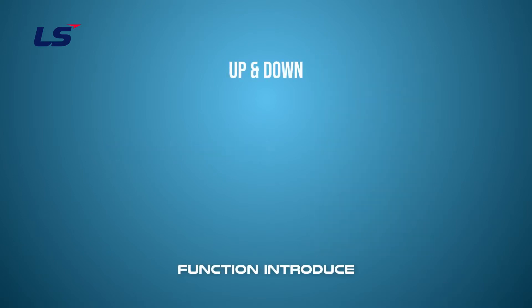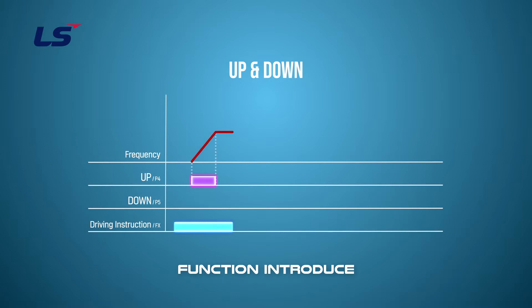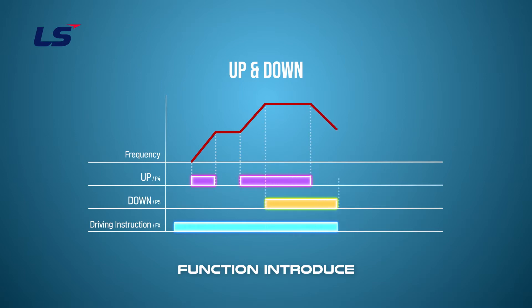The Up-Down operation is a function that enables the frequency reference to be set by multi-function digital inputs. After programming the two multi-function digital inputs to Up and Down respectively, the Run command must be applied, and the frequency reference can be increased or decreased only while the multi-function digital input is on, whether it is Up or Down.